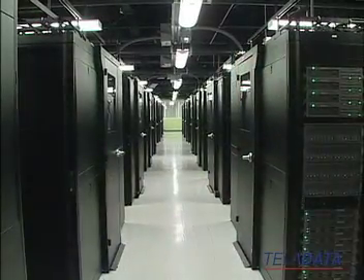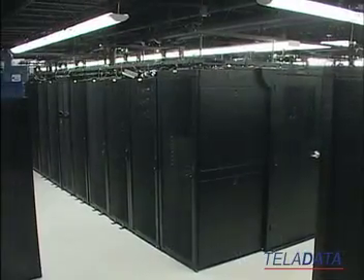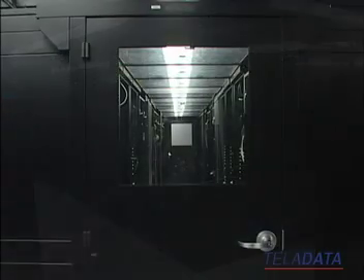So we're at 74 degrees inlet to all of these different pods. And then inside of the hot aisle itself, we'll go take a look at that in a sec, it's between 95 to 105 degrees. Yeah, the whole point is that you're isolating the heat. And when you do that, you can run the data center a lot warmer. And every degree that you increase the temperature in a data center, every Fahrenheit, is a 4% efficiency gain all the way through to the plant.